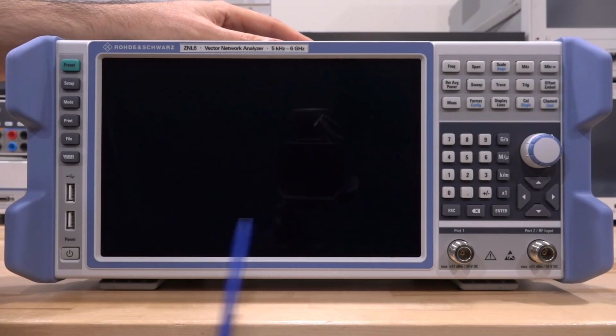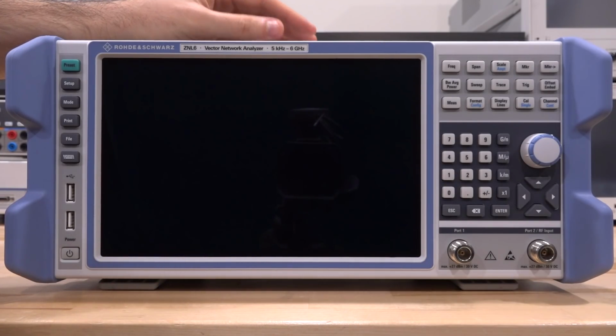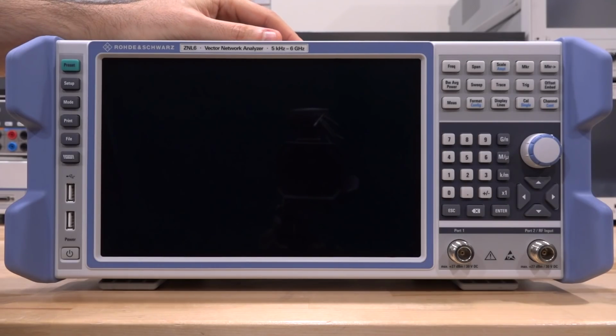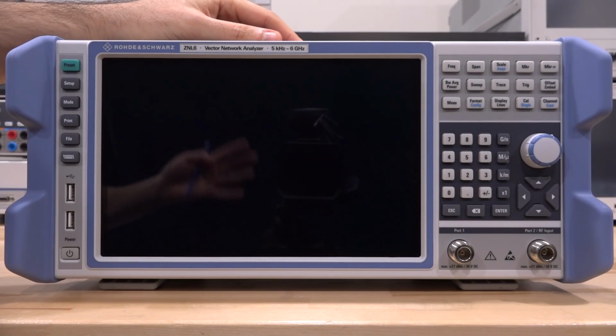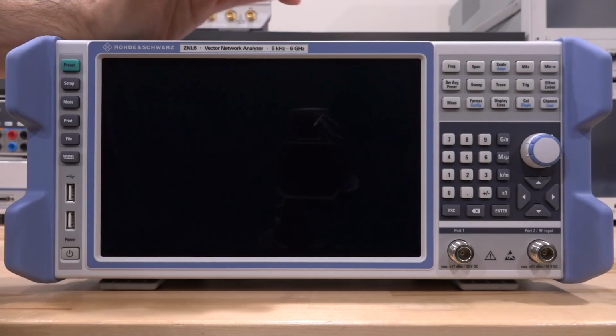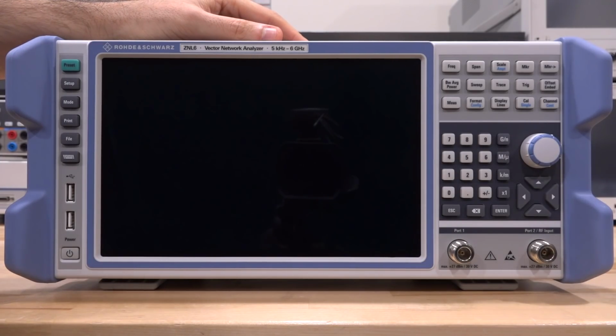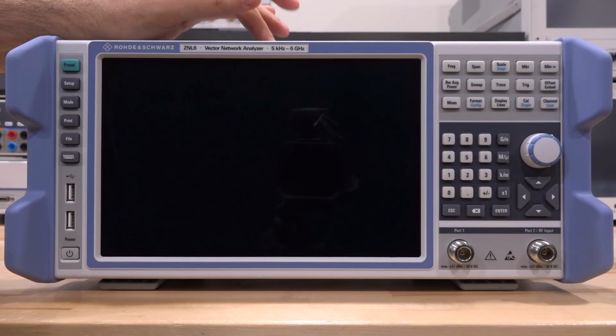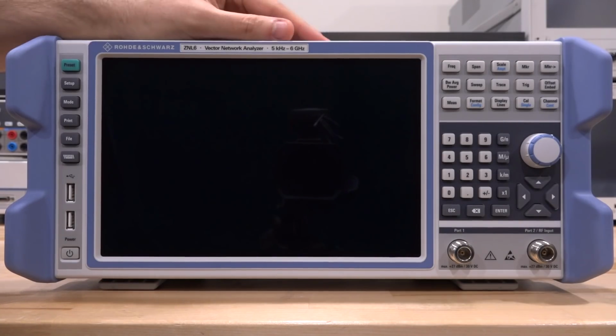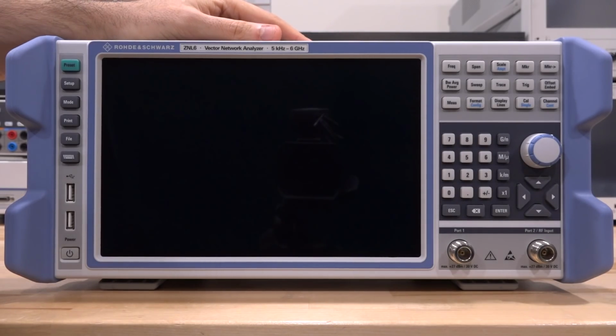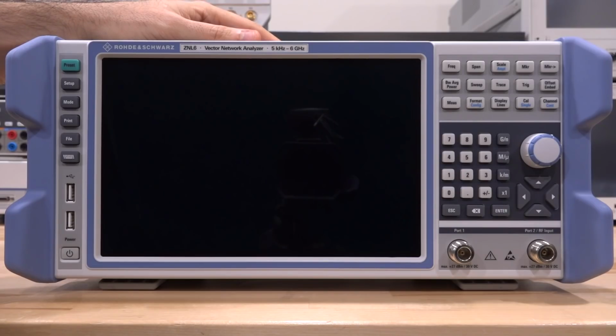In the front, we have the same 10.1-inch LCD screen. This is 1280 by 800 resolution, capacitive multi-touch, and yes, it is still just as reflective, and you can put a screen protector on there to help with some of that reflection. The button layout in this instrument is particularly important because it can jump back and forth between different modes of operation, spectrum analyzer, network analyzer. These buttons are essentially multifunction, and I think they've done a very good job. I do enjoy using this instrument with a mouse quite a bit. I don't really use the touch screen that much, but it is optimized to be used for both.